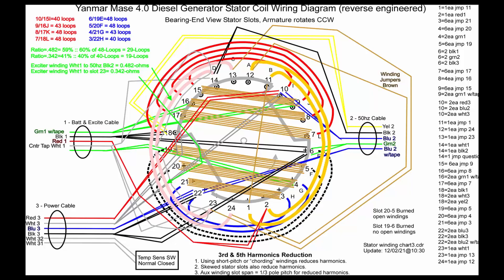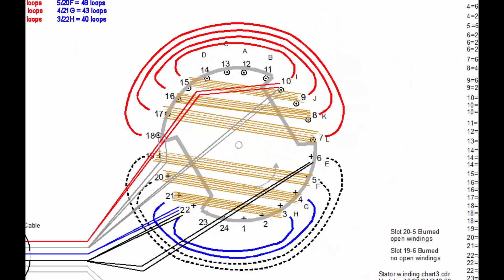There's four red windings at the top, and there's two blue windings at the bottom and two dotted black windings. The dotted black windings are the windings that were burned up when I received this alternator. They would normally be two blue windings also. So basically we have four windings on the top and four windings on the bottom for power generation.